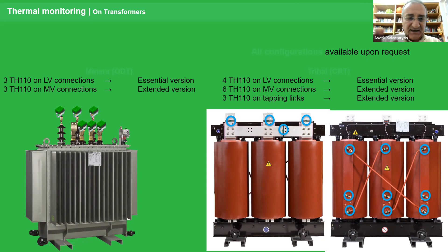Power tags at every bus bar, on every coil, from the front side, from the back side - it's possible to even put tags on the connection rods. These are the rods for seismic protection of the power generators, because they are very heavy, and they must be placed on wheels, because during a seismic shock they must have the possibility of moving in order not to explode or break.